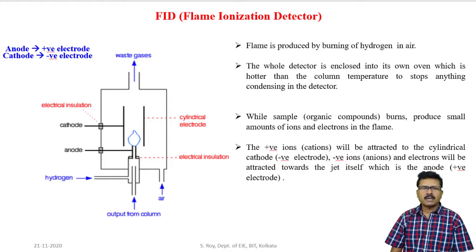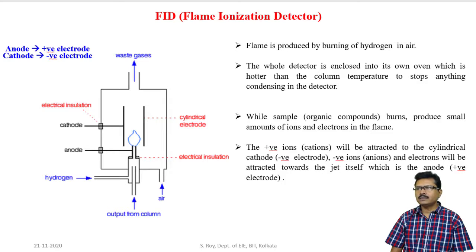First, I am explaining about flame ionization detector. Flame ionization detector is mainly used for organic compounds. In this case, flame is produced with the presence of hydrogen and air — hydrogen is used as a fuel and air is used as an oxidant. The whole detector system is placed into its own oven which is hotter than the column temperature, to stop anything condensing in the detector.